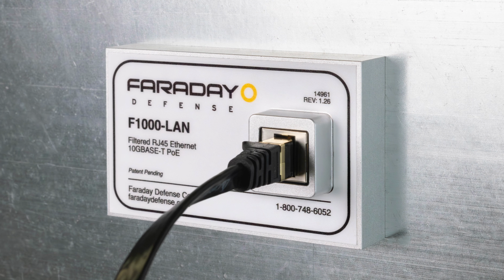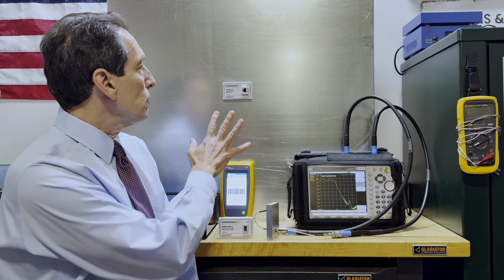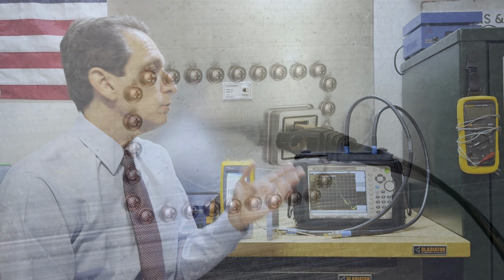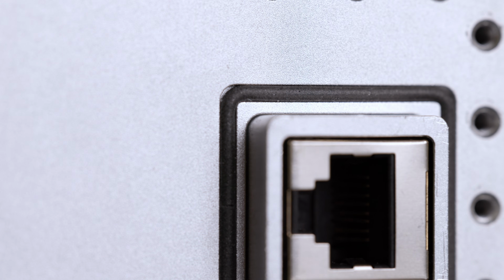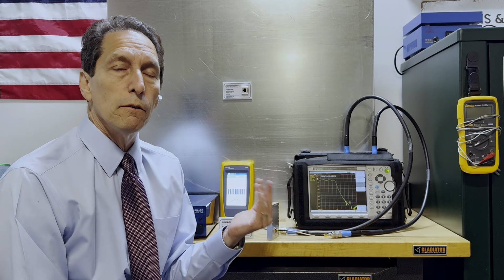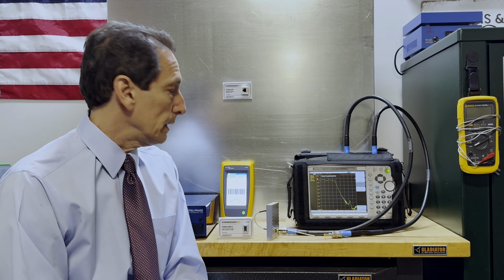Now, these filters are used when you're passing signals in or out of a shielded space, such as a shield room or maybe a shielded tent. They mount directly to the wall of the panel. There are just some screws on the other side that attach it to the wall. They're sealed tightly against the wall using RF gasketing, so there's no energy leakage around the filters. And they provide excellent attenuation of unwanted energy that might get on those cables and pass into the room, or subsequently energy inside the room getting out and radiating away.